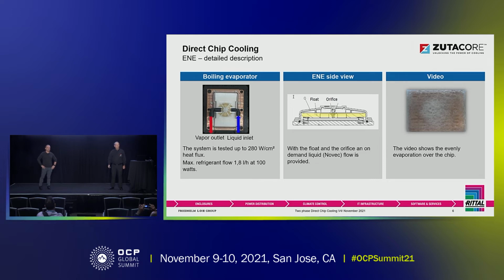The technology is called pool boiling. It boils inside and vapor comes out the red tube that you can see there, and eventually only vapor comes out. What we see in the middle of the slide is that inside that evaporator there is a float that makes sure the pool will be full at all times and that there will be no overflow. So liquid doesn't go in and out - liquid only goes in, and vapor only goes out of the evaporator.